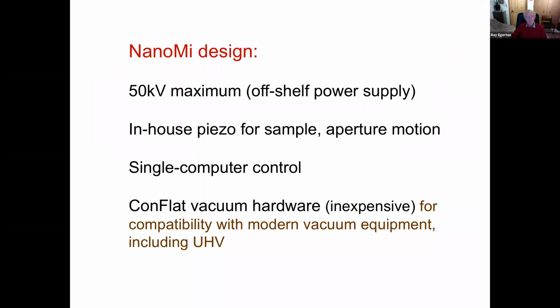Now, NanoMi is going to use electrostatic lenses with an accelerating voltage at the most 50 kilovolts, because you can buy relatively inexpensive power supplies that go up to that value. We have in-house piezo drivers for sample and aperture motion, and the idea is to have the control of the electronics all by a single computer, and to use vacuum hardware based on ConFlat design, which is relatively inexpensive these days and compatible with other vacuum equipment, including UHV.